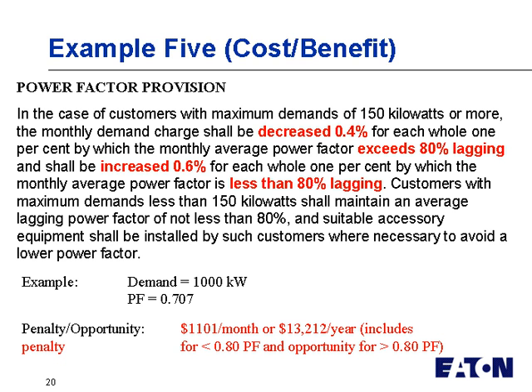0.6%. So for a customer that has a demand of 1,000 kW, there's not only a benefit to bring it up to 0.8, but there's also a benefit to bring it up beyond 0.8. And in this case, you could end up with about $13,212 a year for less than power factor 0.8, and the opportunity of greater than power factor of 0.8. And you're going to wonder why I got that $1,101 or $13,212, and I'll show you some of that later.